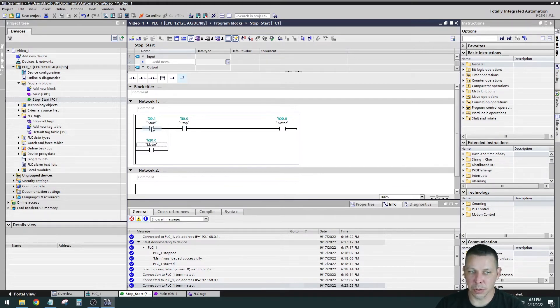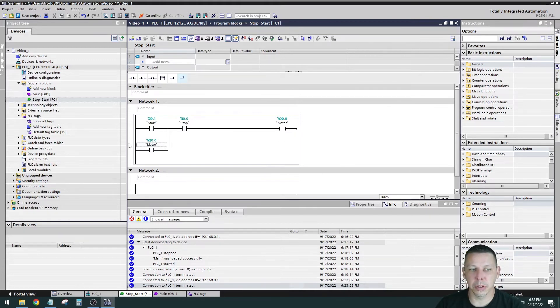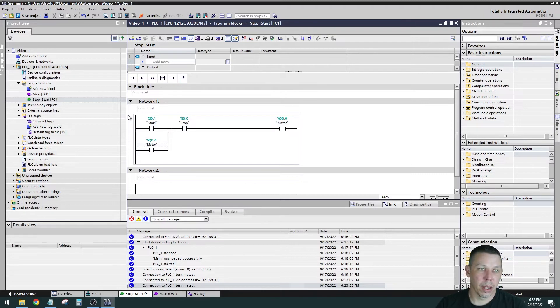Right now we have our Start button as normally open contacts, assuming normally closed contacts on the physical stop button — that's why I left this as normally open. When you energize input I0.1 it hits Start; the stop is closed because of normally closed contacts on the physical stop button. It goes through and energizes the motor. When the motor energizes it closes the branch around the start button, sealing or latching on. Now it won't let us go online because we have different logic on screen than what's in the processor.